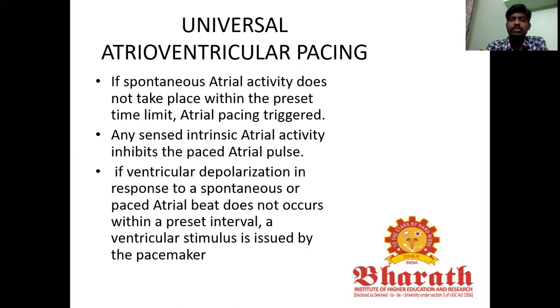If a ventricular depolarization in response to a spontaneous or paced atrial beat does not occur within a preset interval, a ventricular stimulus is issued by the pacemaker. Again, this is one of the major methods used in universal atrial ventricular pacing.